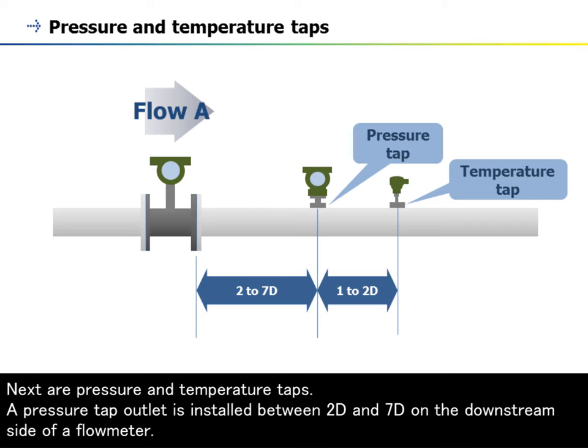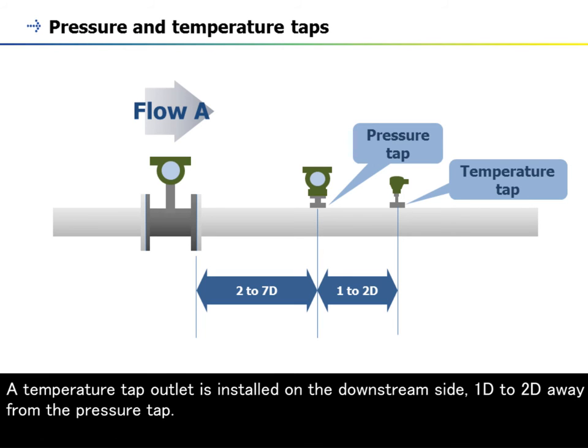Next are pressure and temperature taps. A pressure tap outlet is installed between 2D and 7D on the downstream side of a flow meter. A temperature tap outlet is installed on the downstream side, 1D to 2D away from the pressure tap.